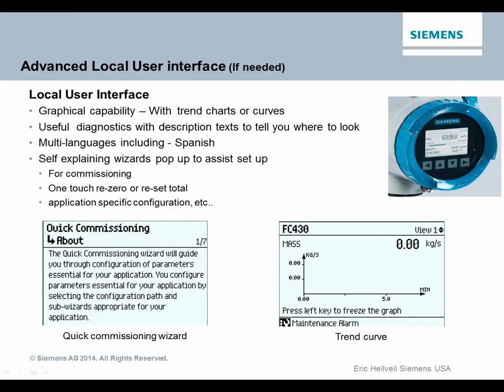You can show, as you see on this display, a flow rate, and a graphical representation with 0 in the middle and negative and plus. This is also showing the density and the fluid temp. This single display can show a single value in 2-inch long block letters with backlighting, so you can see it in total darkness from halfway across the room. You can also see 8 variables: temperature, totalizer 1, totalizer 2, density, volume, all on one display.